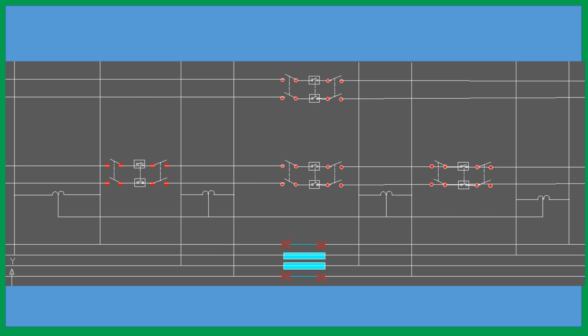In our SP, we have 4 interrupters, but all are single pole. But here all are double pole. Here also there are 4 interrupters, but all are double pole. And instead of a single pole isolator, we have provided a double pole isolator on both sides of the interrupter. So more space is required in this SP and SSP also, because all are double pole. The isolator is also double pole, and your interrupter, circuit all are double pole. So you need more space.